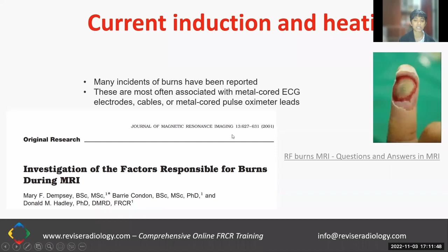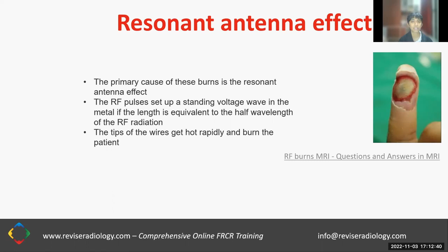The RF pulses set up a standing voltage wave in the metal if the length is equivalent to the half wavelength of the RF radiation. The tips of the wires get hot rapidly and burn the patient. There are multiple theorized causes for these burns, and one of them is the resonant antenna effect. In the resonant antenna effect, the radio frequency pulses set up a standing voltage wave in the metal which is present in the area. This happens if the length of the metal is equivalent to the half wavelength of the radio frequency radiation. Then the metal starts acting like an antenna. The tips of the wires get hot very quickly and burn the patient.